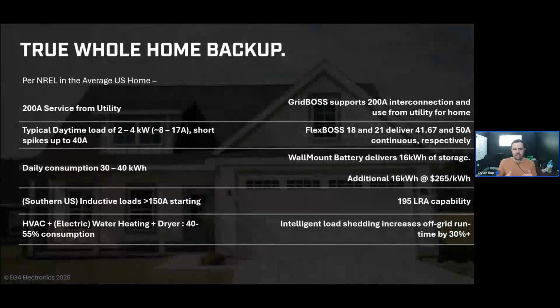And then finally, getting into some high-level applications that I want to talk a little bit about. This is a rehashing of a lot of the things that we've already talked about. Again, why we believe this system delivers true whole home backup, and that really is the main application where we see this system deployed. The system is designed to support a 200 amp service from the utility. It can reliably power the typical daytime load of most US homes that we're going to see these systems deployed on, even considering the high demand points in time of that system.